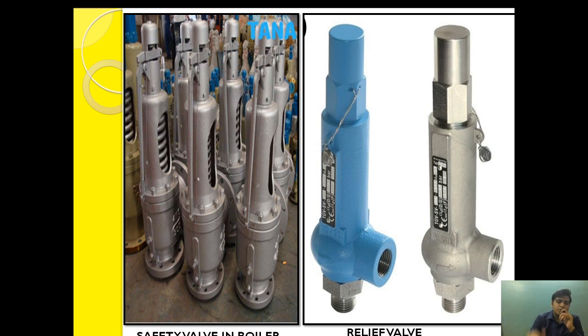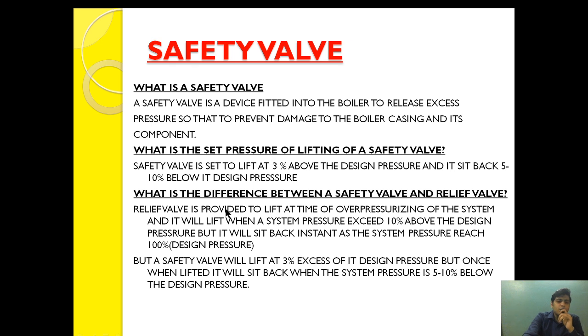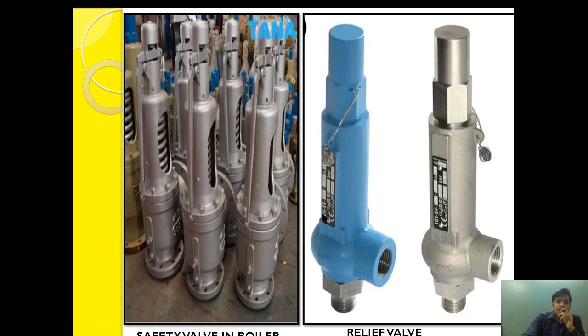Now the question comes to our mind: what is the real difference between a safety valve and a relief valve? Basically, the relief valve is provided to lift at the time of over-pressurizing of the system. It will lift when the system pressure exceeds 10% above the design pressure, but it will sit back as soon as the system pressure reaches the design pressure. The relief valve and safety valve function is the same — to relieve excess pressure — but the mode of operation is different.